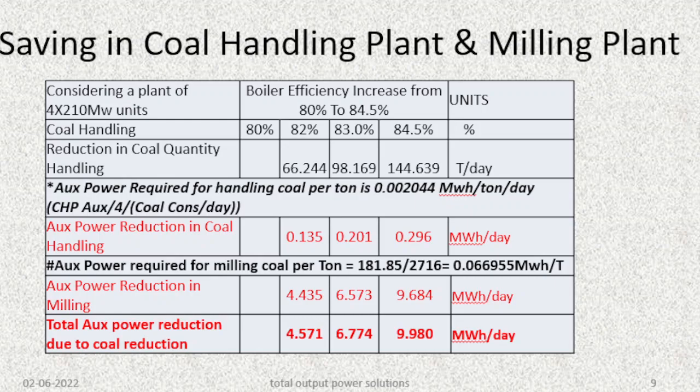Similarly, the auxiliary power required for milling: after the coal handling plant, the coal enters the milling section. Because the fuel quantity has decreased, there will be a reduction in auxiliary power in milling, accounting for around 9.684 MWh per day. The total auxiliary power reduction due to coal reduction would be around 9.980 MWh per day.